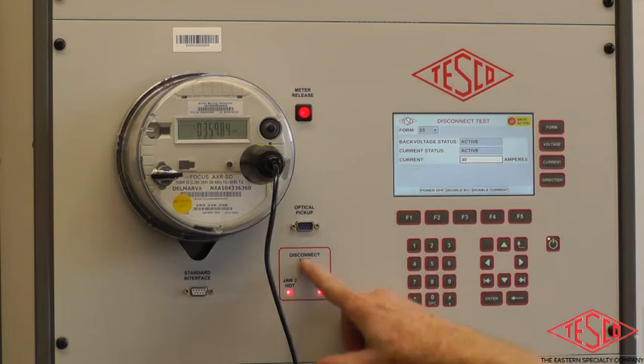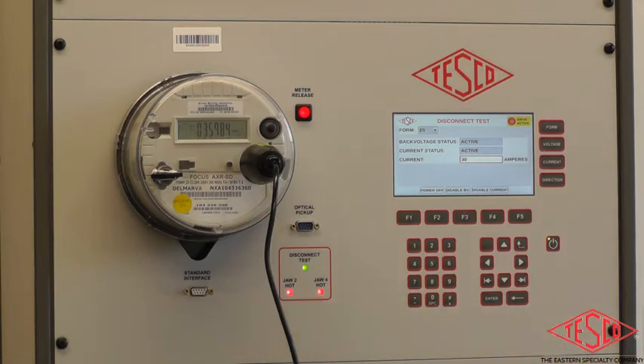As you can see, now that the disconnect is closed, you have jaw 2 hot, jaw 4 hot, and when the switch opens, those jaws will go cold. Now you see the power has come off both of those jaws. This will indicate that the disconnect switch is open. And if we chose to, we could close it now. Well, there's a feature that we want to check, and that is where there's a back voltage. It will not close on it.